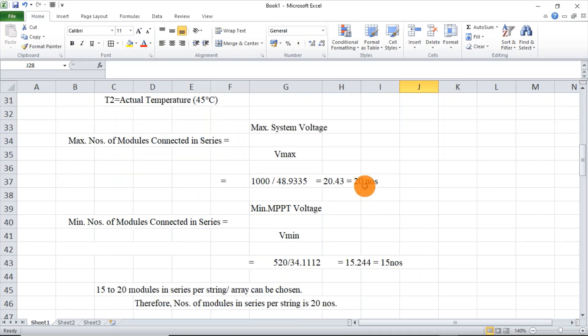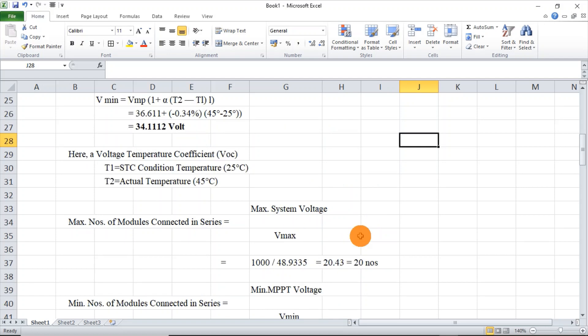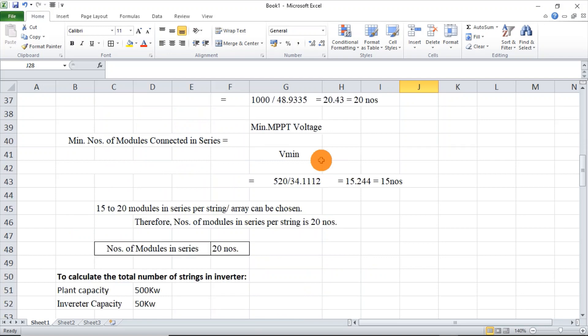For the minimum number of modules to be connected in series, we take the minimum MPPT voltage, which is 520V, divided by Vmin, which we calculated as 34.1V. Equating this gives 15.2, that is 15. So a minimum of 15 modules should be connected in series to this inverter.